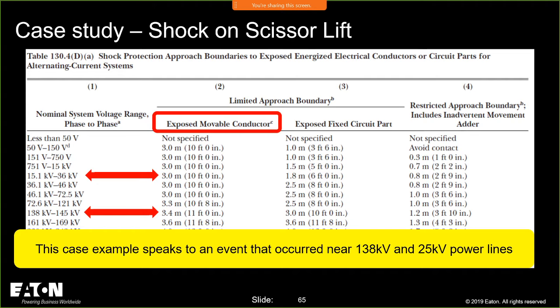Now, what about the exposed movable conductors? A really good example of exposed movable conductors are your power lines and things of that nature that are energized. They're not insulated, and they can sway with the wind. I may have a conductor that I haven't terminated that could move. That would be an exposed movable conductor. If I have things fixed in place, then I'm at a fixed, and I'm at 3'6". The moment that energized part can move, I'm moving out to 10 foot. And look at this, 10 foot all the way up to 72.5 kV.